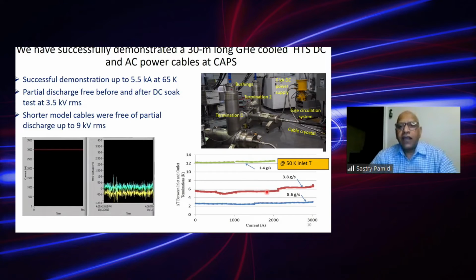So this is an example of a 30-meter long superconducting power cable that we built and demonstrated using helium gas as the cooling medium. As you can see, these are the terminations of the cables, and this is the cable. It makes a long loop and comes back and joins here as a 30-meter cable. And we use a Stirling system to cool, and this provides about 250 or 300 watts of cooling power around 50 Kelvin. And in the back you see there is a 6 kiloamp DC power supply that is used to test the cable. So the cable was tested at multiple flow rates.